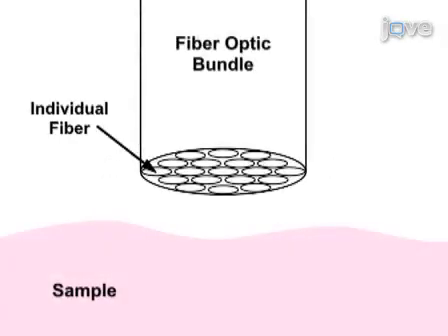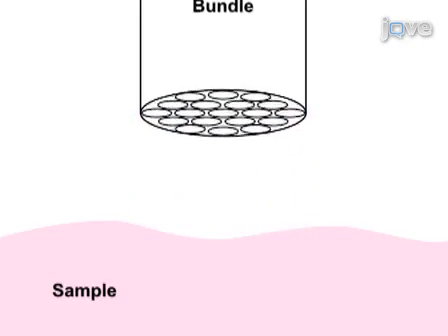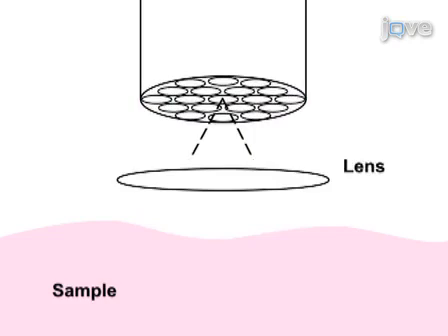The spatial resolution of the microendoscope can be increased by attaching a micro lens or lens assembly to the distal tip of the fiber bundle. These optics are configured such that instead of placing the bundle tip directly onto the tissue, the tip is imaged onto the tissue surface with demagnification, thereby increasing the spatial sampling frequency imposed by the light guiding cores of the fiber bundle. The degree of demagnification corresponds to the increase in spatial resolution and at the same time to a proportionate decrease in field of view.